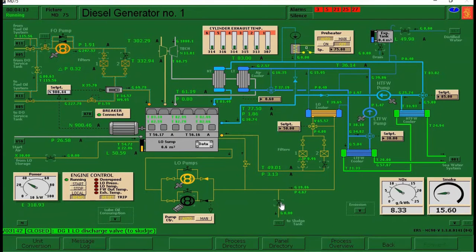So our discharge valve here is closed, our filter open, so we should keep in mind that our discharge valve here should always be closed because it will drain the lube oil here in our sump and it will cause a low level alarm here. We have power generated. Okay, our valves from the service tanks are open.